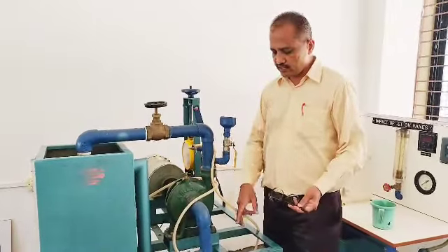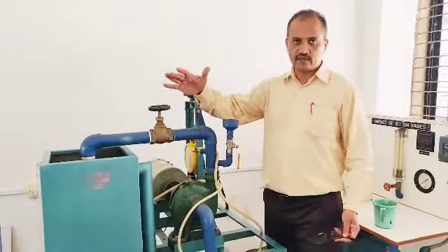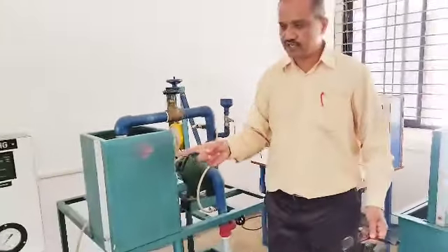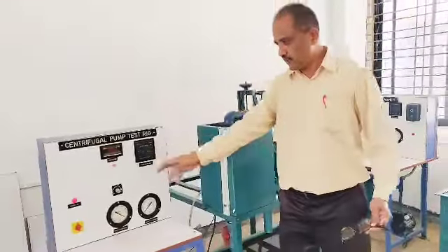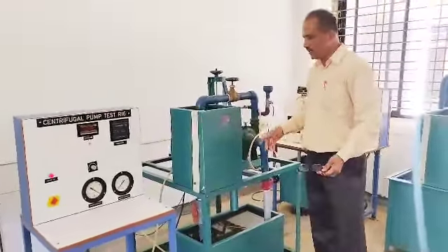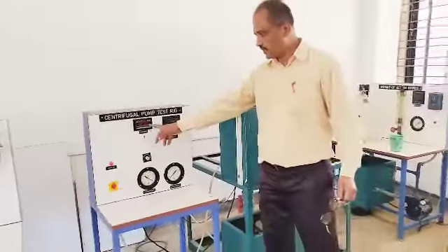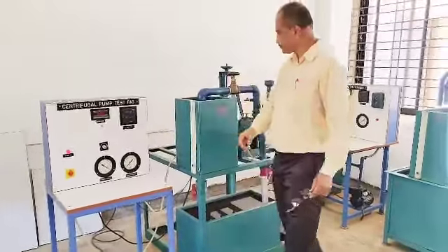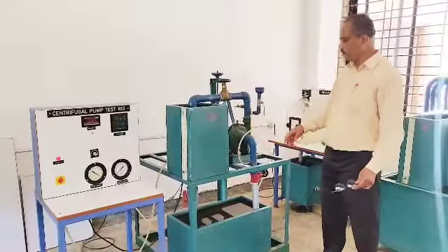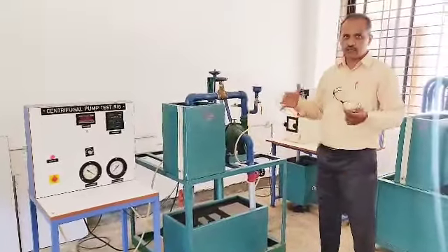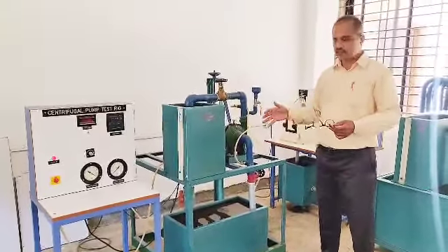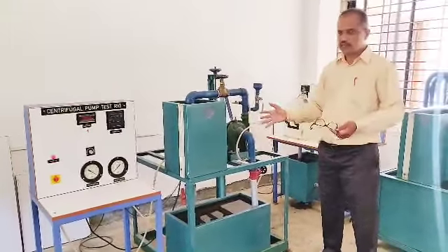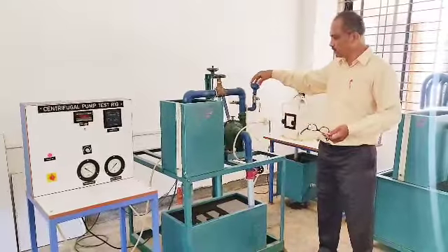So what I will do, I will start the pump at, say, 1500 RPM. I will take the readings of the suction pressure, delivery pressure, and the power produced. Then I will increase it to, say, 1800. Again, I will see the digital RPM, then I will see the power produced and these readings of suction and delivery pressure. This way, I will take some 4-5 readings, and I will plot the efficiency of the centrifugal pump with respect to the speed.